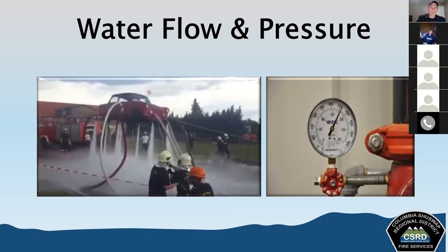We need to understand that with normal consumption, there can be peaks and there can be valleys, but normal operating pressure occurs at what could be called regular consumption. So, you know, at 2 o'clock on Wednesday afternoon, how much water is flowing through the system at that point in time. This is measured by connecting a pressure gauge to the hydrant during normal consumption, and we do that when we do our flow tests on the hydrants.